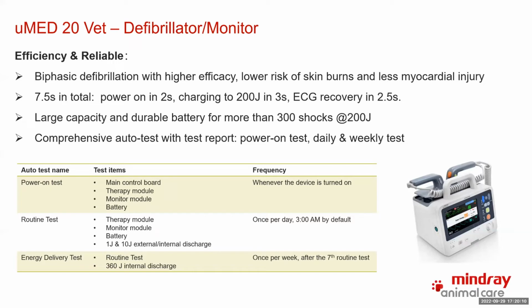Turning on the machine only takes 2 seconds. Charging to 200 joules only takes 3 seconds. And the ECG recovery takes 2.5 seconds. So that's 7.5 seconds in total, which is the fastest in the industry right now. The uMED 20 vet also provides a large capacity battery for operation, so it can support more than 300 shocks at 200 joules. But as I mentioned before, normally for vets there's no need for 200 joules, so it can support many more shocks for the patient.